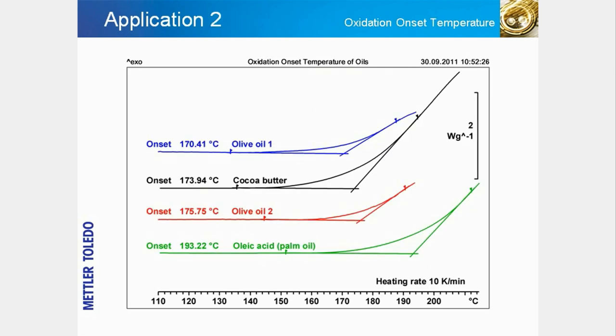The thermal and oxidative stability of materials is a very important quality characteristic because many materials decompose at higher temperatures and become unusable. Stabilizers are often added to counteract this effect. The thermal stability of a substance can be measured by using a purge gas that reacts with the sample — in most cases, oxygen. This slide shows an example of the determination of the oxidation-onset temperature (OOT) of different edible oils. The sample is placed in an open crucible with unrestricted access for oxygen gas, and the temperature is ramped at a constant rate until exothermal decomposition begins. The oxidation-onset temperature is evaluated as the onset in the measurement curve.